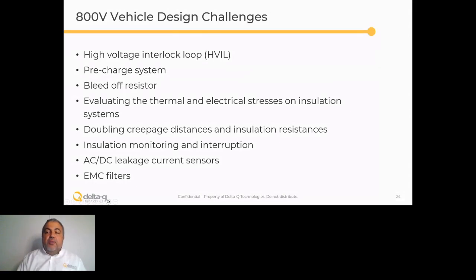The high voltages and noisy environment in the drive systems require robust and high-performance galvanic isolation to ensure safe and reliable operation. Often, the creepage distances and insulation resistance need to be doubled compared to 400 volt systems. And in particular, there is a need for developing and producing a class of 800 volt EV cable capable of properly handling voltages up to 1,000 volt peaks.